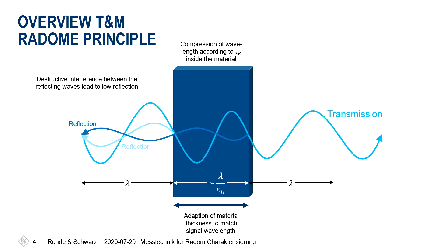The second way to measure permittivity is by measuring the phase. Inside the material, the wave travels at a different speed — no longer at the speed of light — and that causes a phase change. So there are actually two ways of characterizing the material: first, through the resonance frequency, and second, through the transmission phase. Both ways are possible with the QAR50.